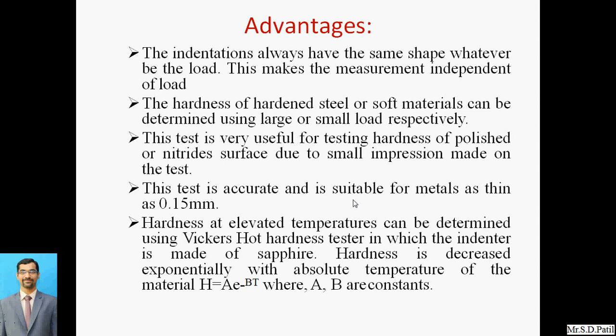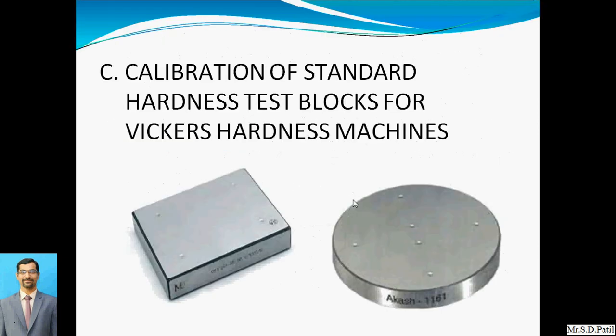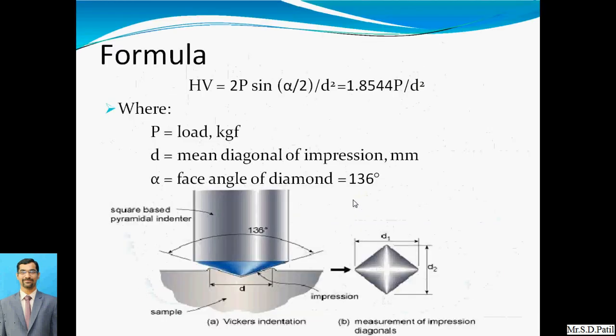For hardened steel we can go with the larger load, and for soft material we can go with the small load. So this test is very useful for testing the hardness of polished or nitrided surfaces due to the small impression made on the test. In Brinell hardness testing we are using the ball indenter, and that's why the penetration surface is larger.